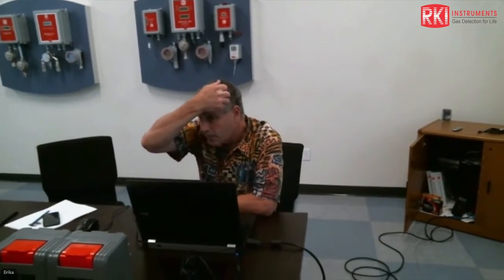I just wanted to let you know, I was using the GX 6000 charger plugged into the SDM, and then when I changed it with the SDM charger, the screen came on. Oh, so good. It actually gives power to the cal station if you use a separate charger, but it won't turn the screen on. That's what the problem was. I think it's a lower voltage. I think that's probably why you had enough voltage to get a power LED, but not the screen. So that's good. Gotcha. Yep. So good to go. Very good.